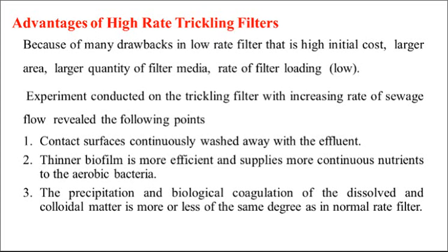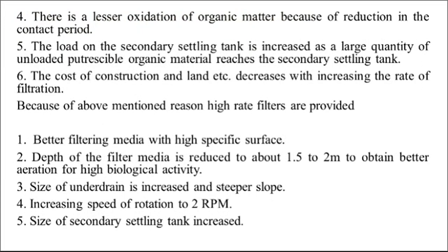First one, contact surfaces are continuously washed away with the effluent. Thinner biofilm is more efficient and supplies more continuous nutrients to the aerobic bacteria. The precipitation and biological coagulation of the dissolved and colloidal matter is more or less of the same degree as in normal rate filters. Fourth important point, there is a lesser oxidation of organic matter because of reduction in the contact period.